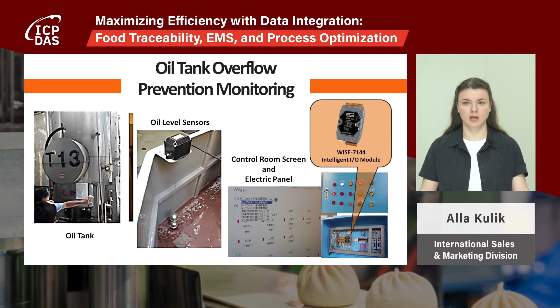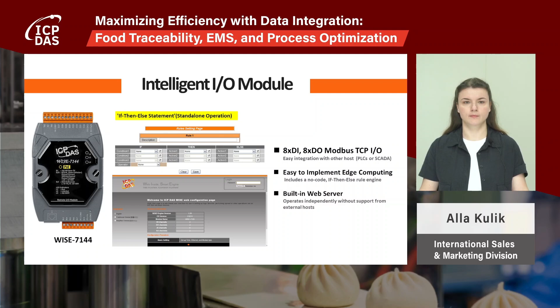The WISE-7144 is an intelligent I/O module featuring 8 digital inputs and 8 digital outputs with Modbus TCP I/O capabilities, enabling seamless integration with external hosts like PLCs and SCADA systems. It also supports edge computing with a no-code interface. Its if-then-else function ensures that necessary actions are taken even if the connection between the WISE-7144 and the control center is lost, maintaining continuous operation and safety. With its built-in web server, the WISE-7144 can operate autonomously without the need for additional support from external hosts.